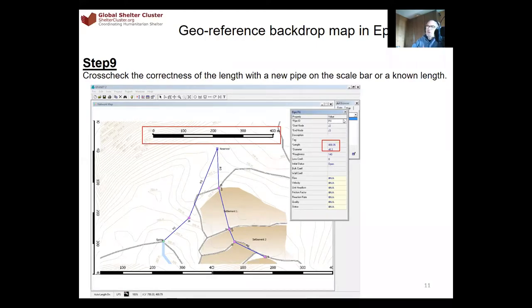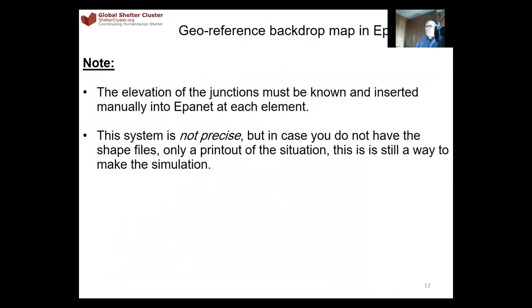This process saves time because you don't have to manually calculate pipe lengths. Of course, it is not a very precise process, but if the length is slightly off — even by one or two meters — the friction losses of the pipe do not change too much. Elevation is more important than pipe length. But this system is very easy and quick when you have no other option.